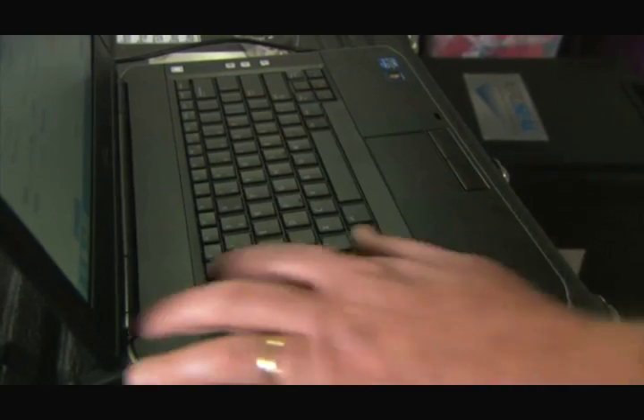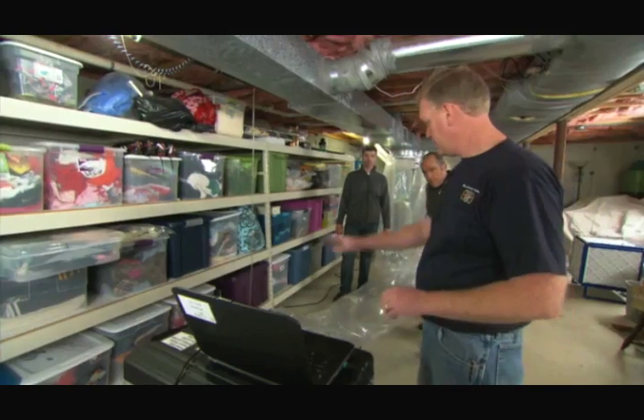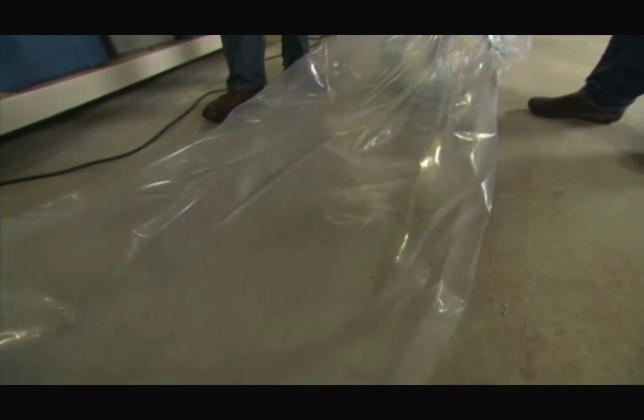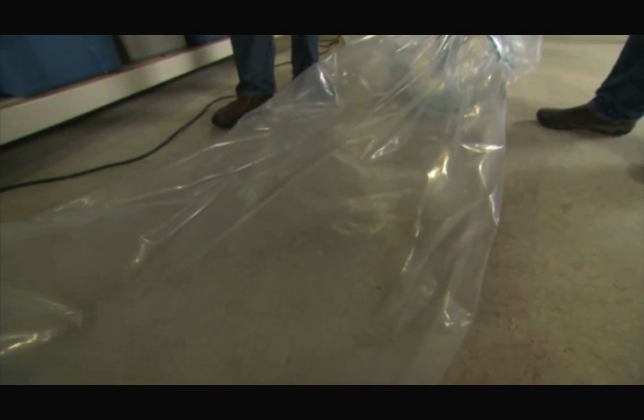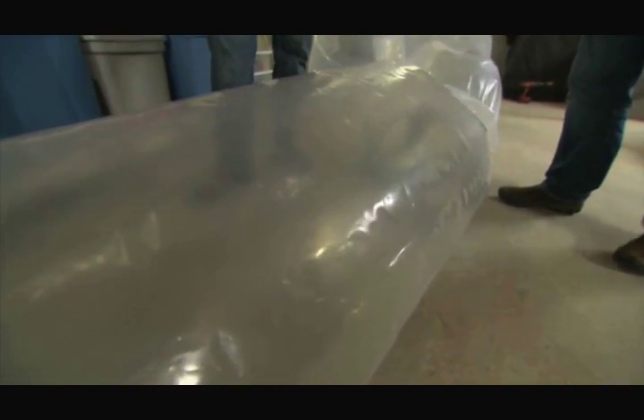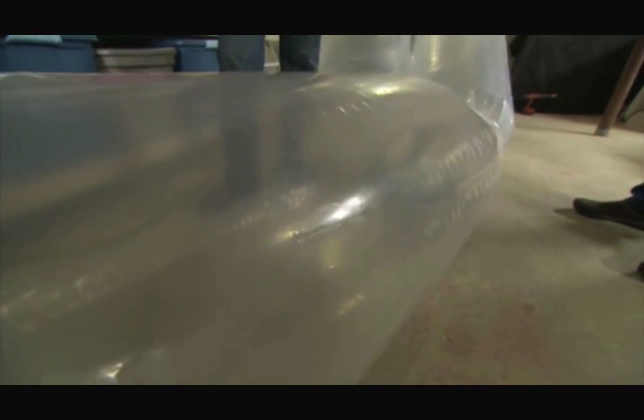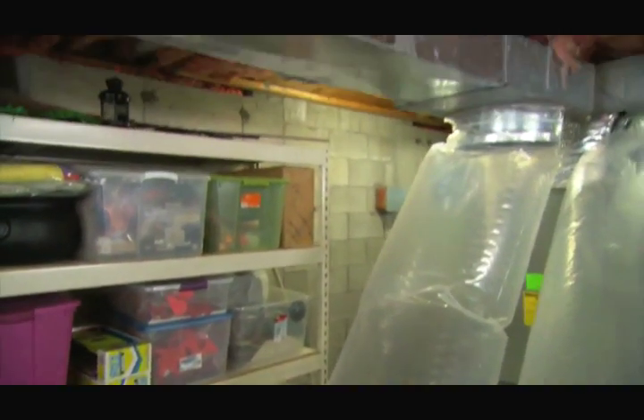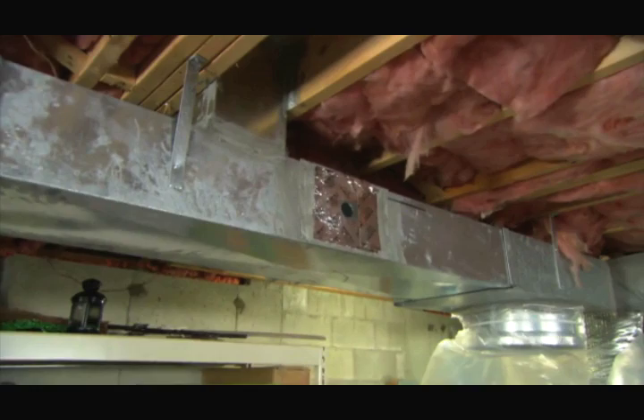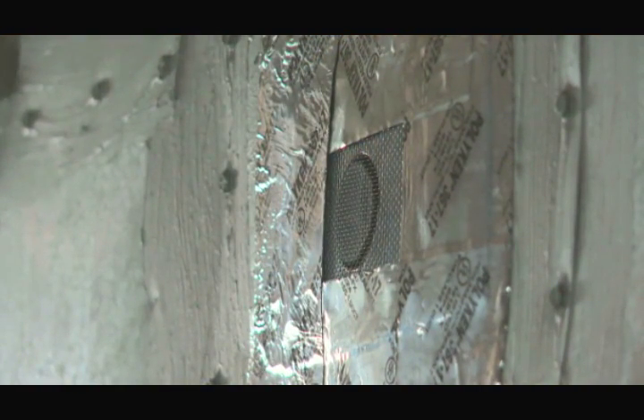We are. Let her rip. So we'll activate the machine. The fan will turn on, and it'll start to inject the sealant. Here it comes. Right now, the airborne sealant is flowing through the pressurized ductwork, and it's squeezing out just where there's an opening in the ductwork.